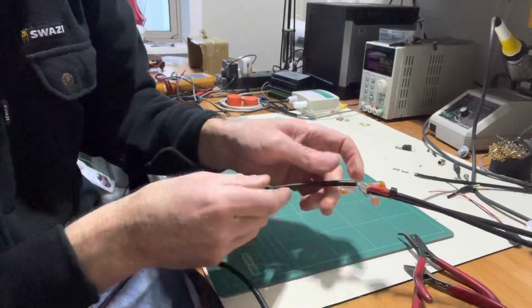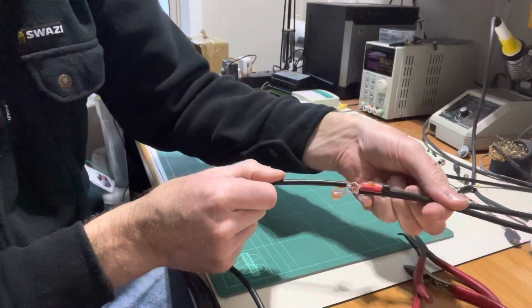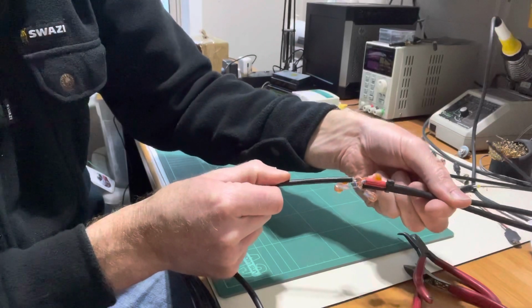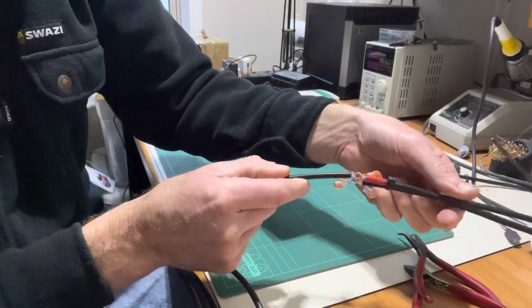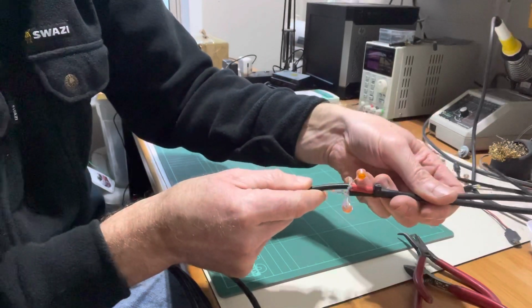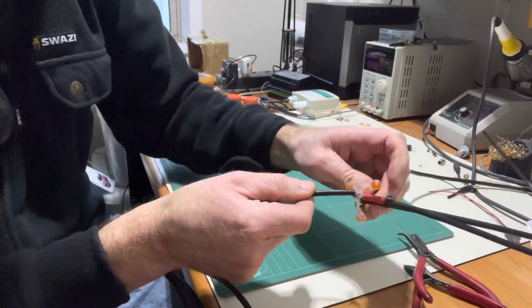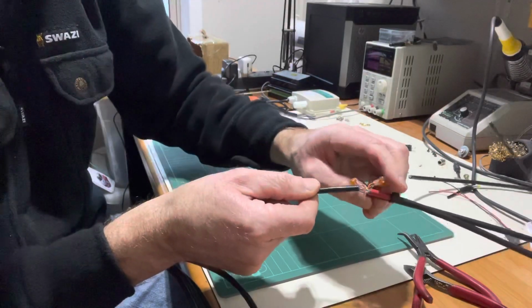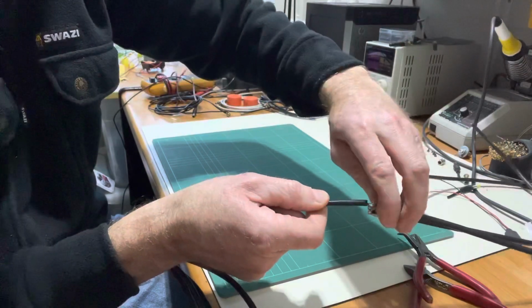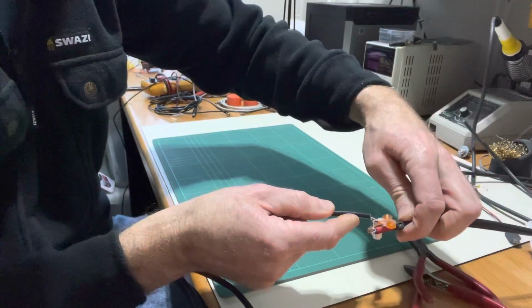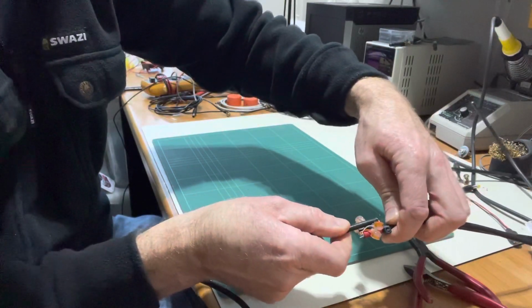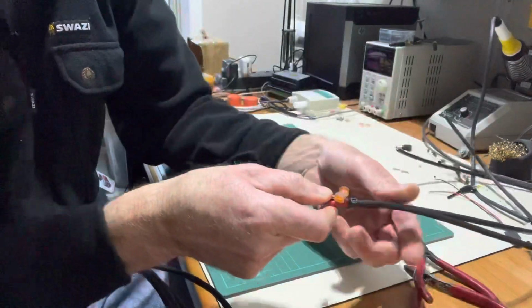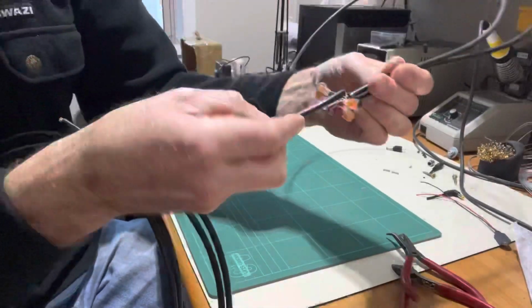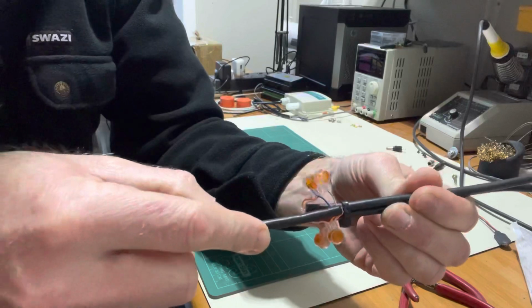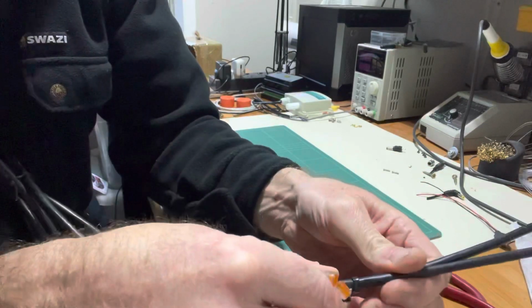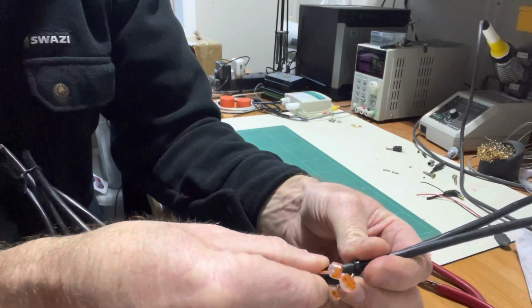The issue here is that there's no physical strain relief between the two. So sometimes what you can do, I'll take all these connectors out the same way. If you've had enough length in the cable, you can push the two ends past each other and then cable tie through there.